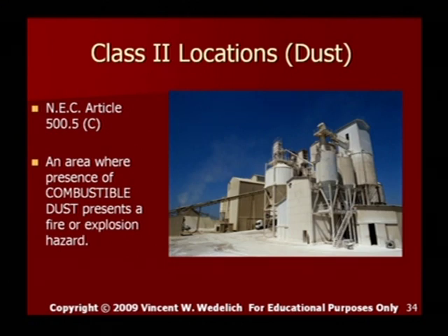We had an Imperial sugar factory here in Texas that had little chain-link fenced areas. They had motor starters that were not installed in the proper type of enclosure, which we'll cover later. One of the vendors that kept going in and out of there was saying, "Hey guys, you're not doing this correctly. You could create a fire." And sure enough, they did actually create a fire.